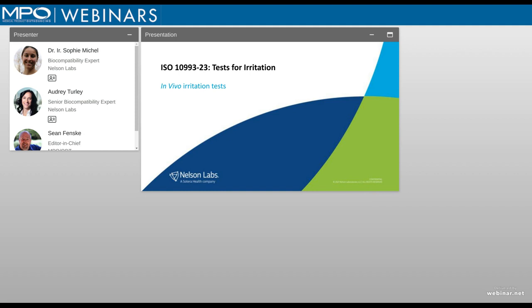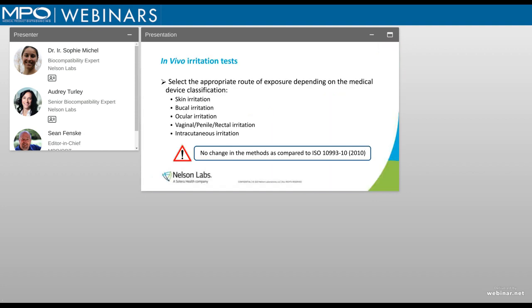We also want to briefly mention the in vivo irritation tests, because they are still an important part of the assay of the standard. And like Sophie mentioned, there are some applications or locations where a device will be used where a clinically relevant irritation site or analysis site should be selected. Right now, we don't have an approved tissue for that for the in vitro method. I will say they are being developed. I know the tissue manufacturers have several available, they just have not been validated for medical devices.